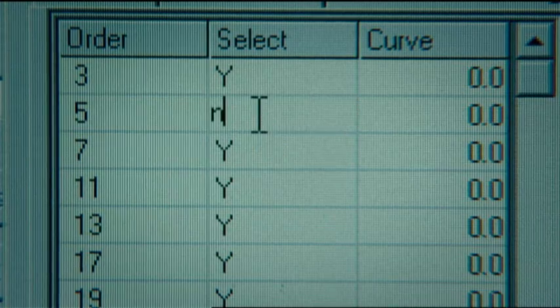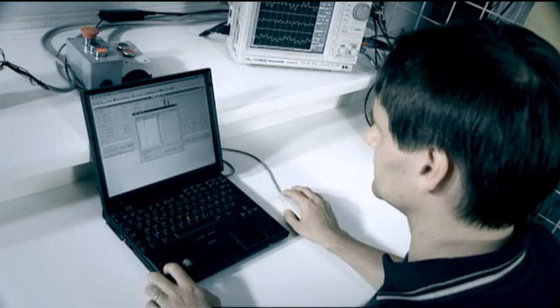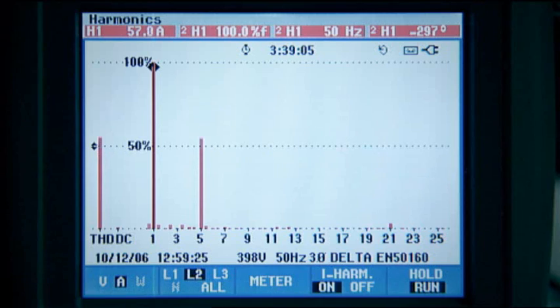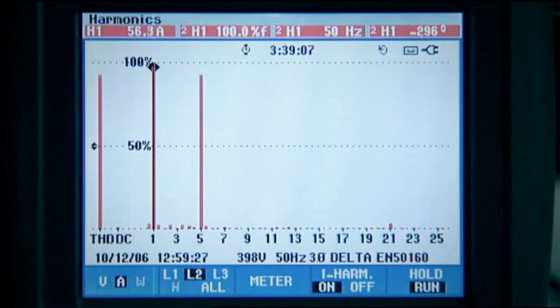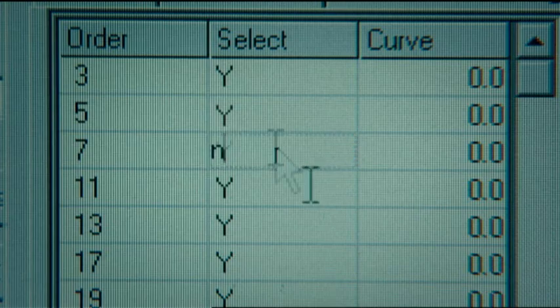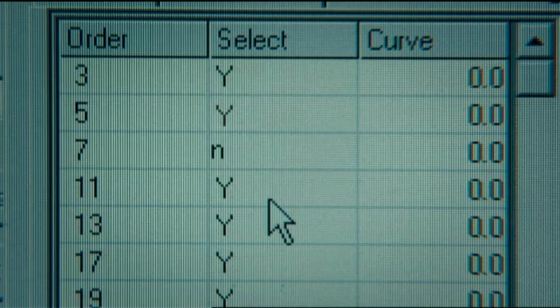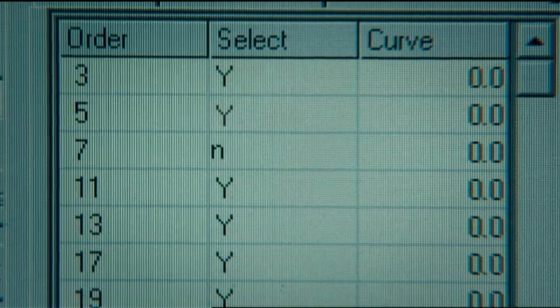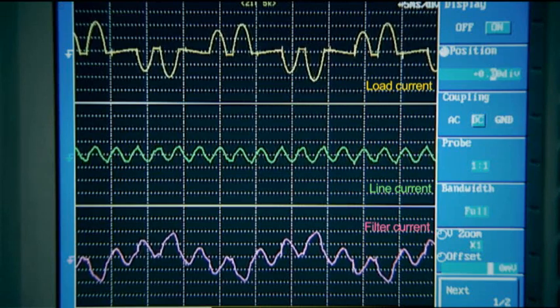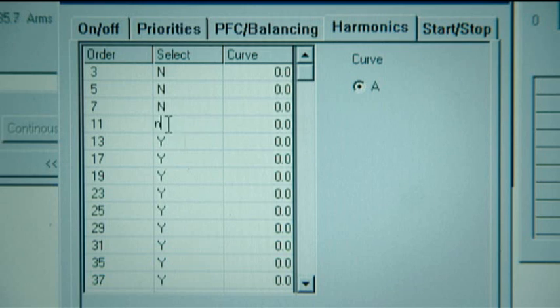The active filter was performing maximum filtering and reactive power compensation. We will now deselect the 5th harmonic. This means that only the 5th harmonic is flowing in the line. The same happens if we only deselect the 7th harmonic. Only the 7th harmonic appears on the spectrum and in the line.